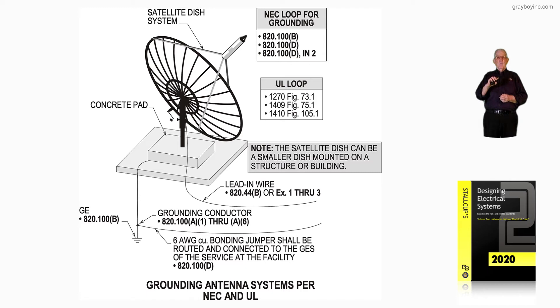The grounding conductor is discussed in detail in 820.100A1 through A6. With this information, what we're saying is you can't ground that dish and then use the shield or sheath of a cable to serve as a grounding means. You have to ground it properly.